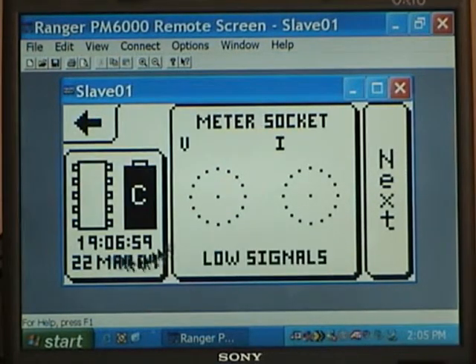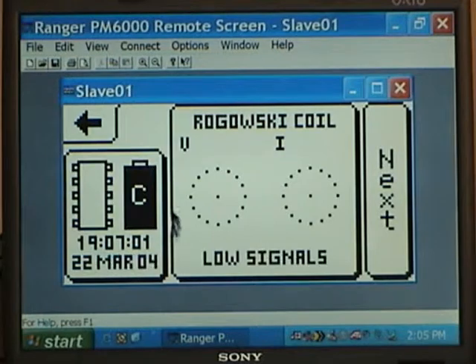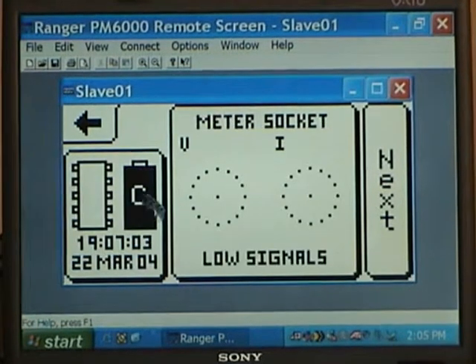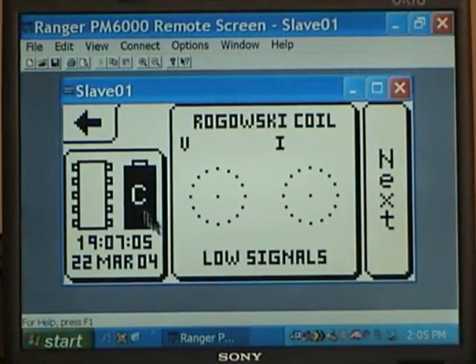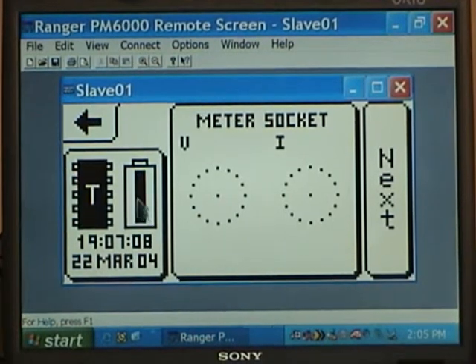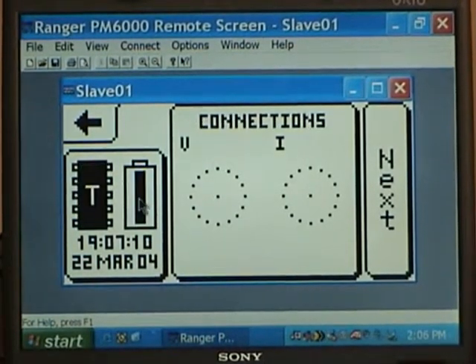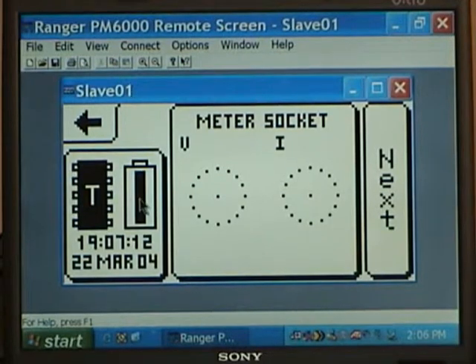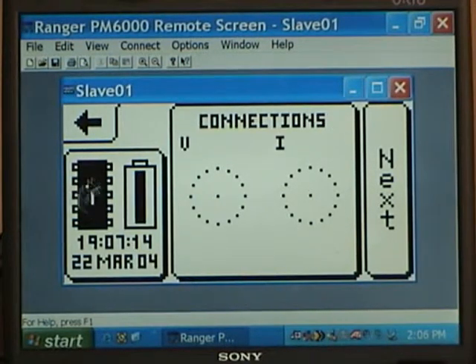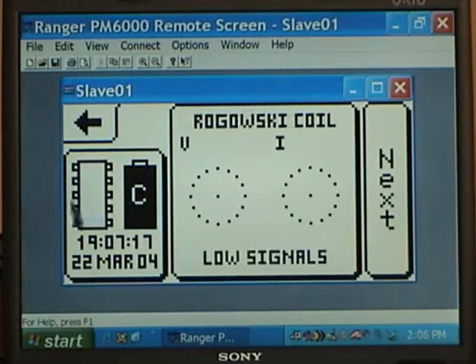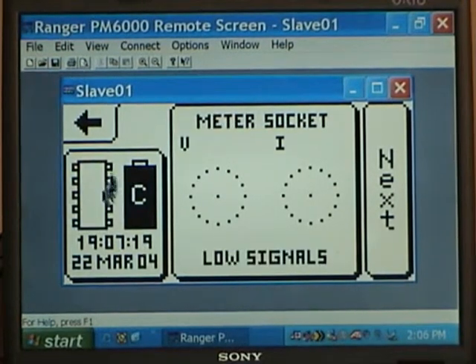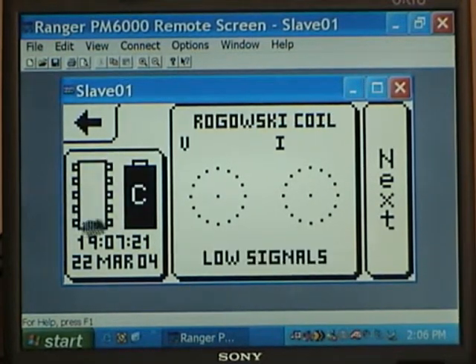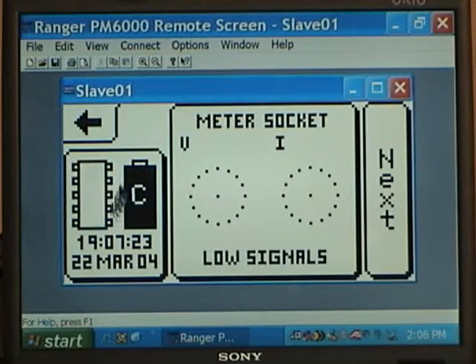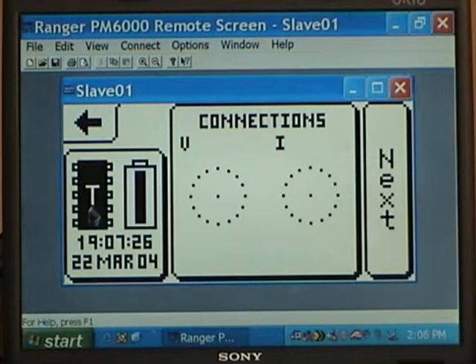And over here you see an icon that signifies that the battery is charging, so we do have power from L1 to neutral. This is what keeps the unit running and where it receives its power from. Here we show the microchip memory here with a T on it, meaning that the unit is timing out because it does not see a current load yet. And so remember, after 15 minutes it will start recording voltage only, but as soon as there's a current load that appears, it only takes 1 minute and then it starts itself recording.